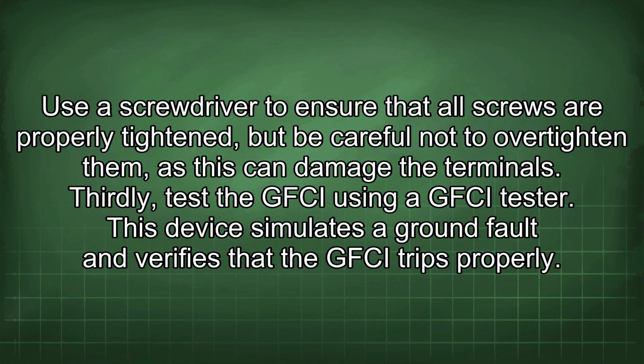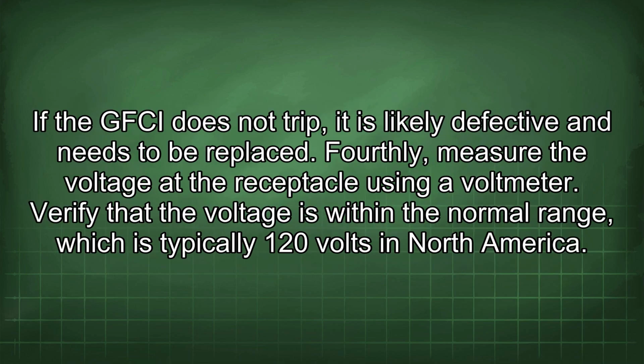This device simulates a ground fault and verifies that the GFCI trips properly. If the GFCI does not trip, it is likely defective and needs to be replaced. Fourthly, measure the voltage at the receptacle using a voltmeter. Verify that the voltage is within the normal range, which is typically 120 volts in North America.